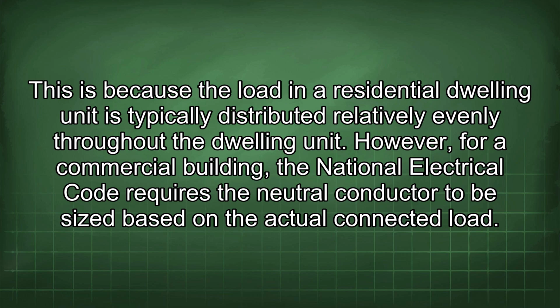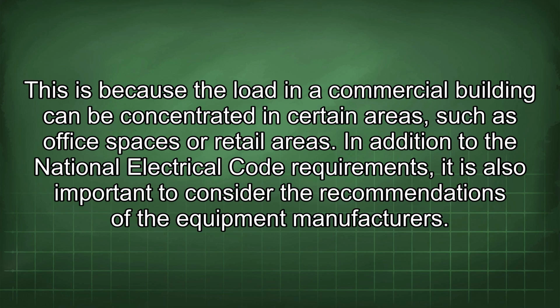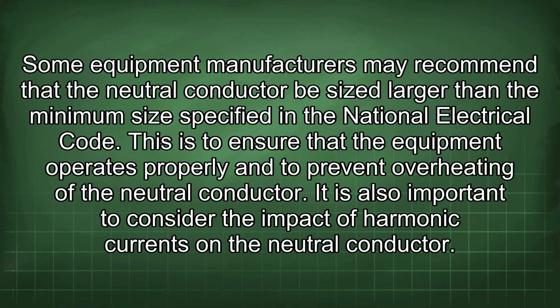However, for a commercial building, the National Electrical Code requires the neutral conductor to be sized based on the actual connected load. This is because the load in a commercial building can be concentrated in certain areas, such as office spaces or retail areas. In addition to the National Electrical Code requirements, it is also important to consider the recommendations of the equipment manufacturers. Some equipment manufacturers may recommend that the neutral conductor be sized larger than the minimum size specified in the National Electrical Code. This is to ensure that the equipment operates properly and to prevent overheating of the neutral conductor.